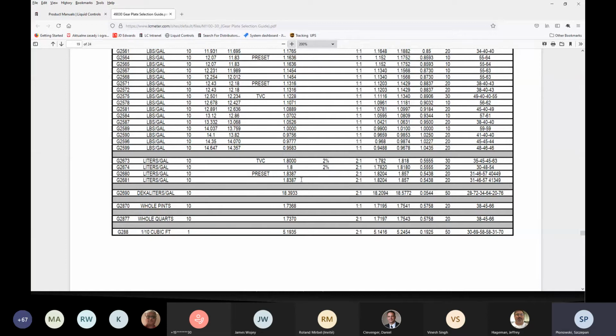You see a whole bunch of information across, but for us, probably one of the more important things is that this gear plate requires a 2-to-1 ratio. So if you're doing any field conversion and your meter has a 1-to-1 ratio, you would have to change it to a 2-to-1 ratio. It gives us what the ratio of the gear plate is here, 1.8387. That tells you that's the output ratio of that gear plate.